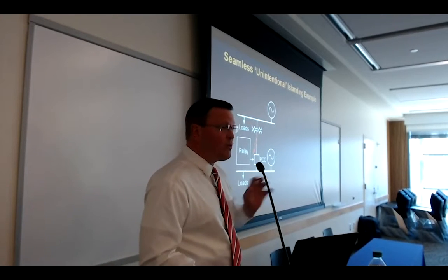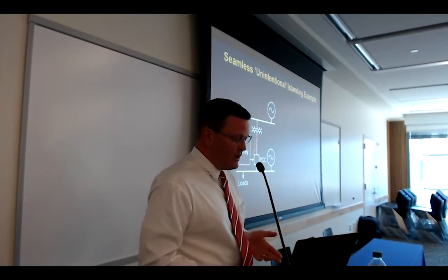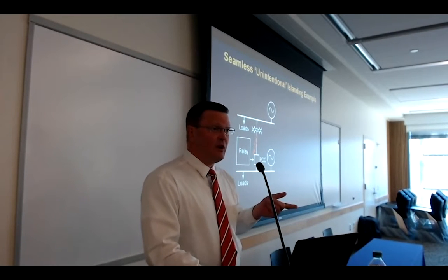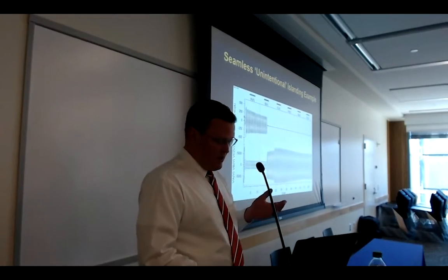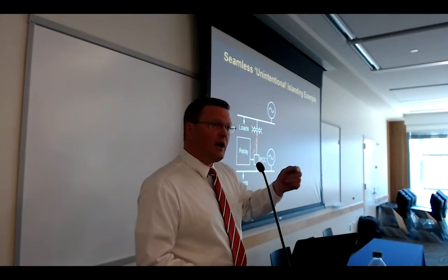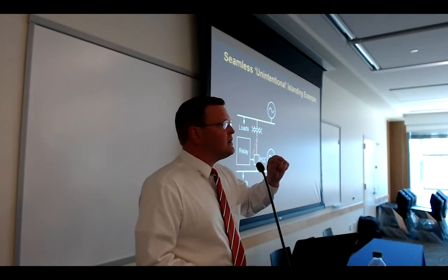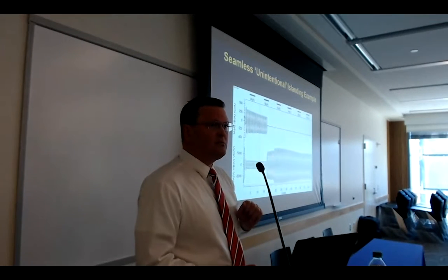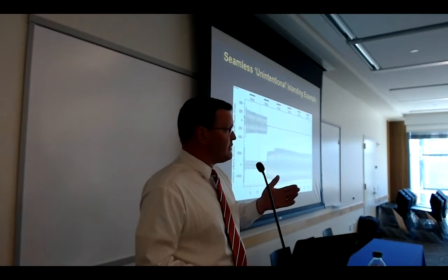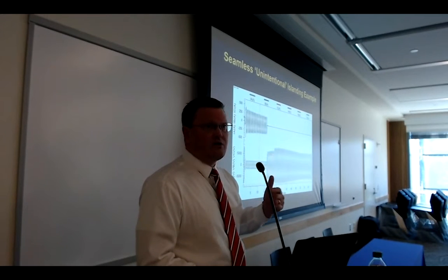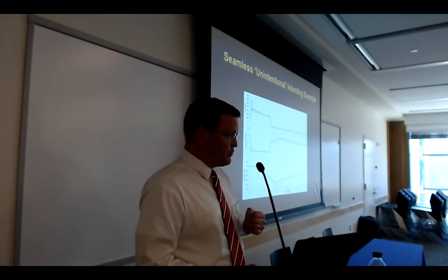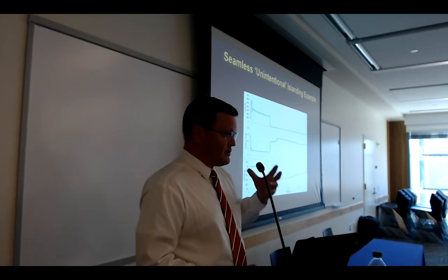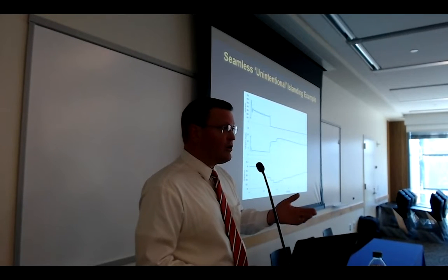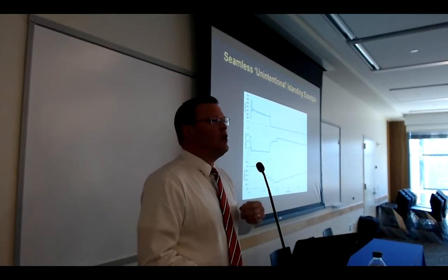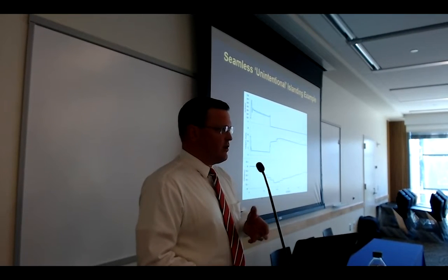So let's talk about what this looks like. One of the things we do with relays that you may not be aware of: first of all, you've got here an example of a microgrid connected to the bulk electric macrogrid. Here's an event where there was a fault on the line between said macro and microgrid, and the relay recorded an event. The top line is the oscillography of current, the bottom the three-phase oscillography of the voltage, converted to single-phase or to RMS values. Here shown in blue are the current, the voltage, and the frequency, the three main parameters.